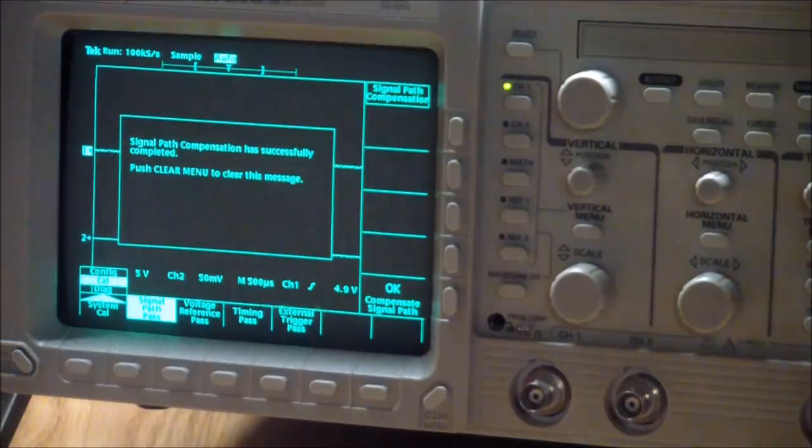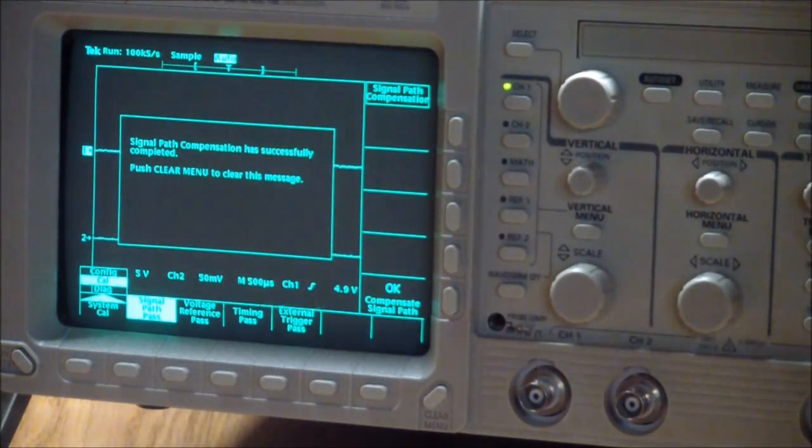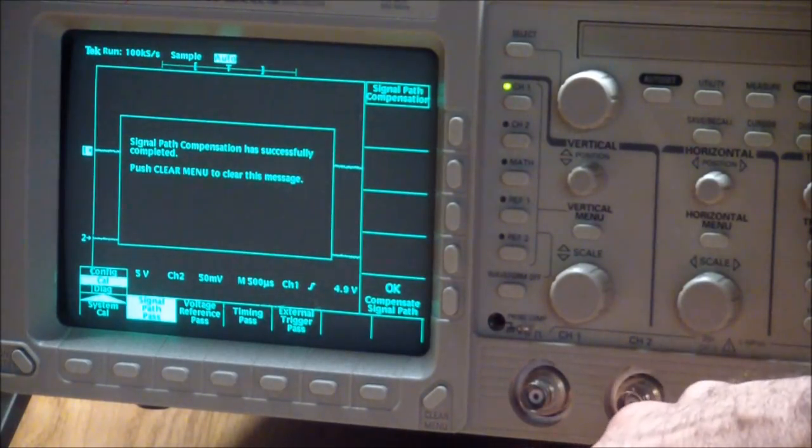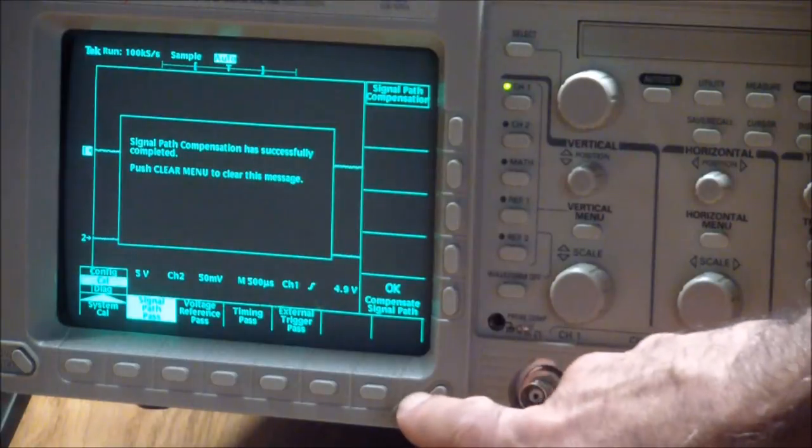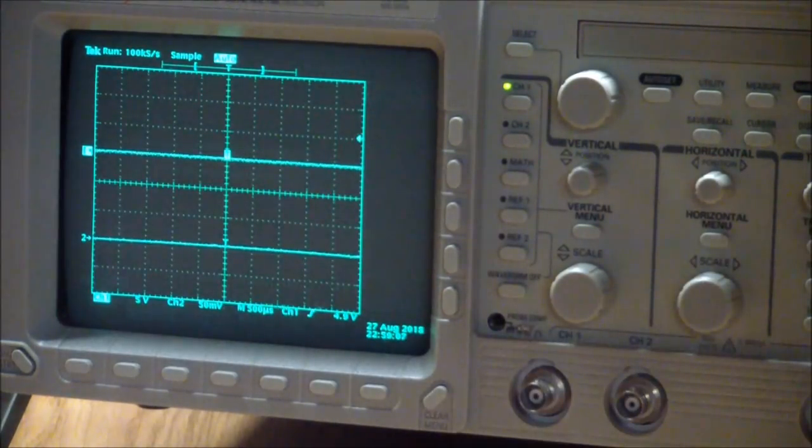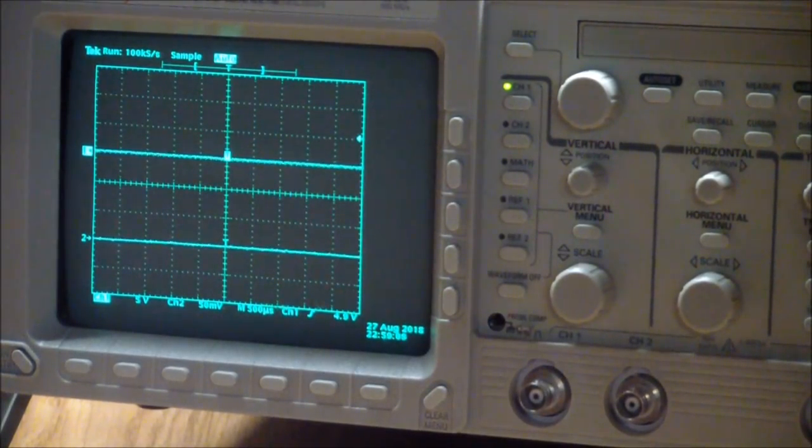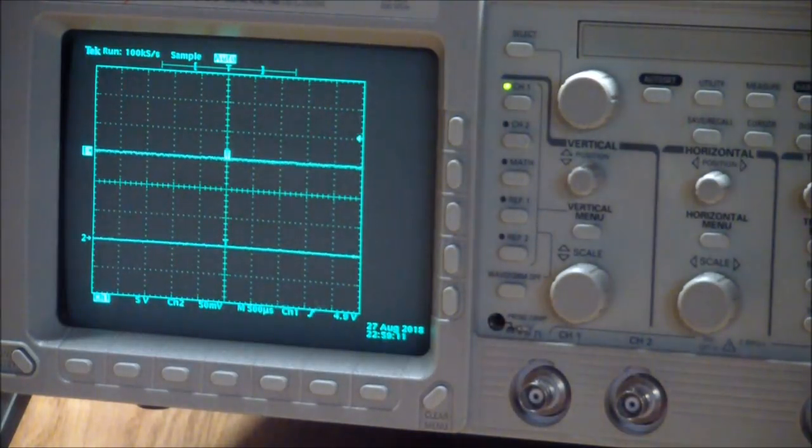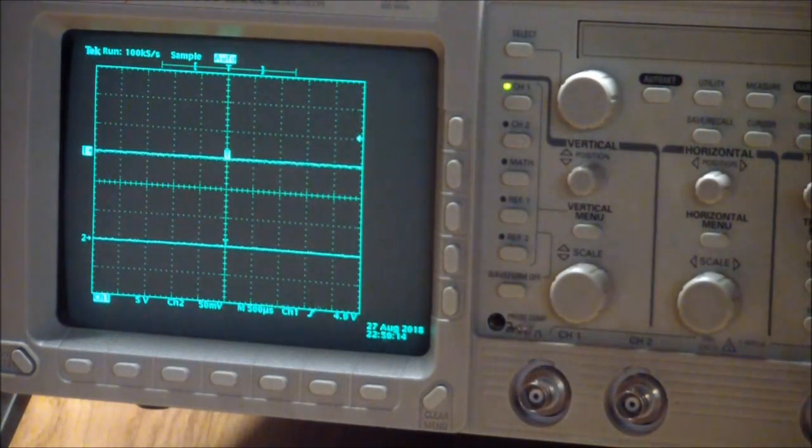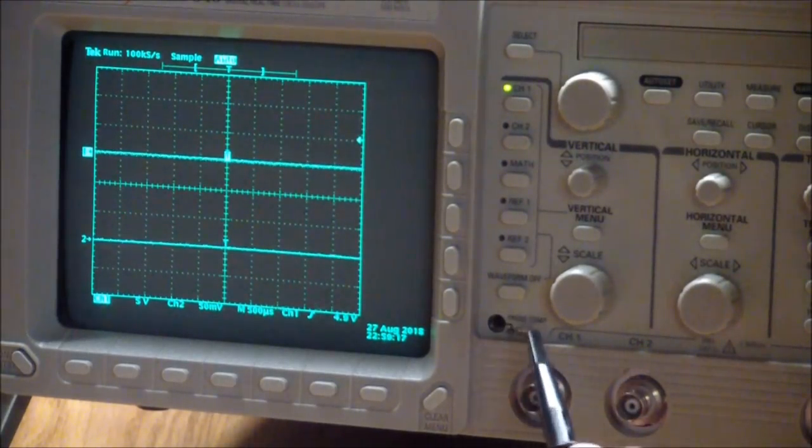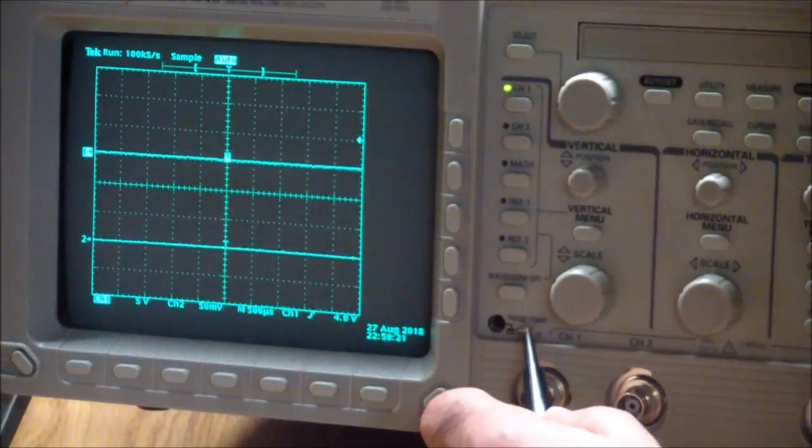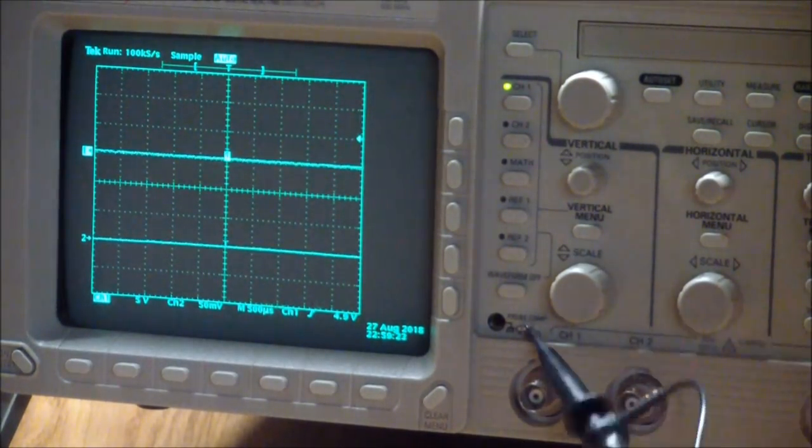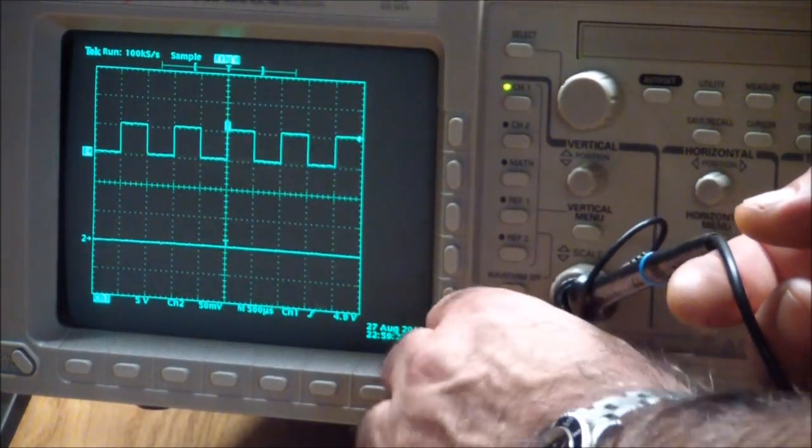So it successfully did the signal path compensation and what we need to do now is push clear menu. And that's it. As the last thing let's check the compensation signal, not no the calibration signal.